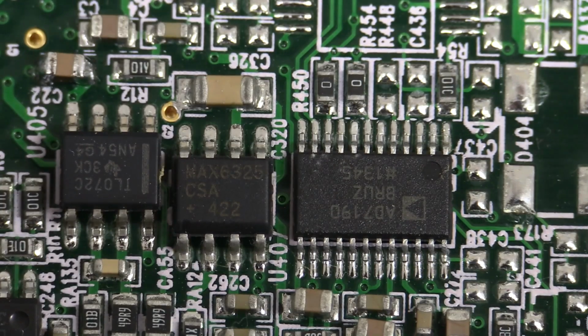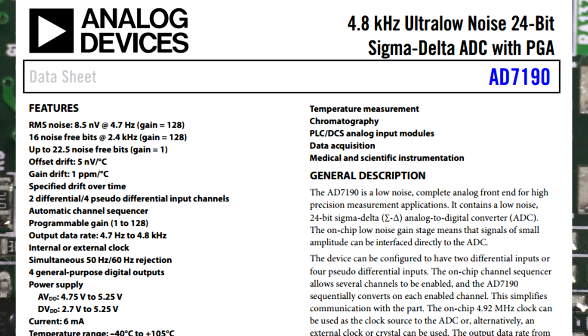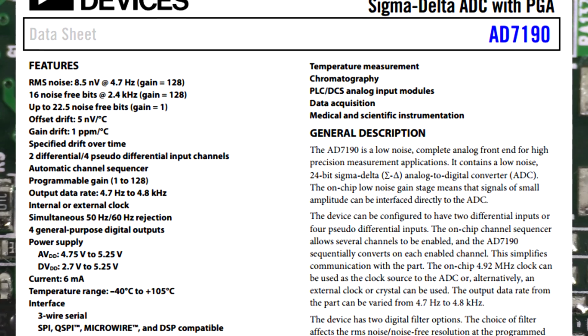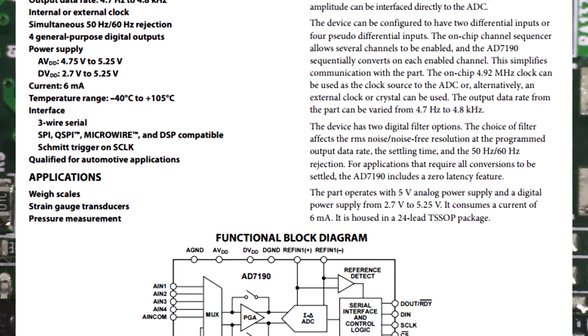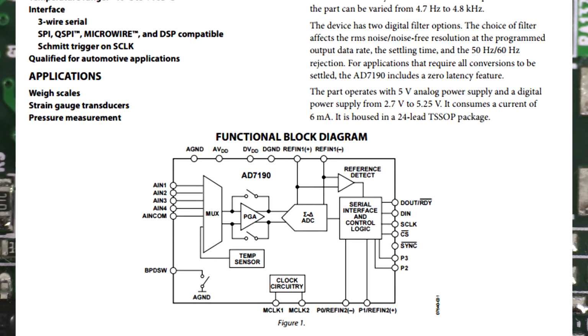And there, folks, is the money shot. There's our ADC, an Analog Devices AD7190, a 24-bit Delta Sigma converter with a 4.8 kilohertz conversion rate and 4 channels. It's got a built-in programmable gain amplifier, yada yada yada. Fairly typical of what you'd expect in a 5.5 digit multimeter. Of course, unlike Fluke and Keysight, they haven't rolled their own dual slope converter - just used an off-the-shelf Delta Sigma. Good enough for a 5.5 digit meter, no worries whatsoever.